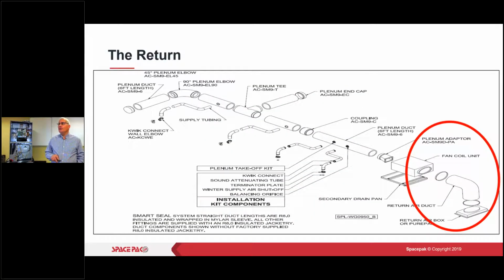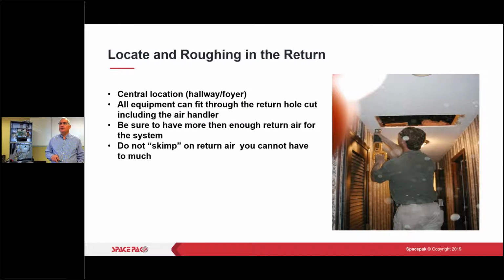Now in our world of returns, it's going to be smaller than what you're used to, but it's not based on volume. And you don't have to worry, you can never have too much return. We get a lot of jobs where it is open to the second floor, so you may have a foyer that's open all the way up through the second floor. Guys ask me all the time, can I do 2 returns? Not a problem. You can do 2 returns. You can never have too much return air here, so it's not an issue.